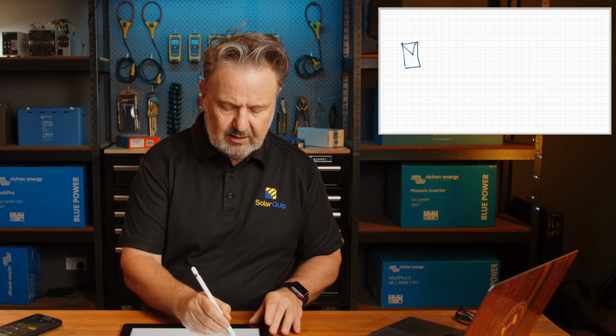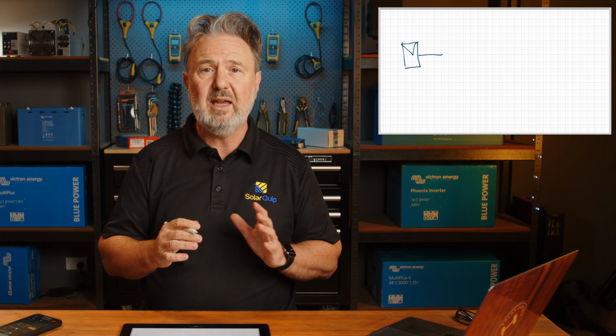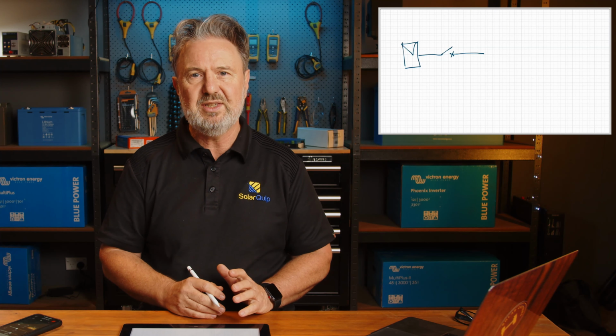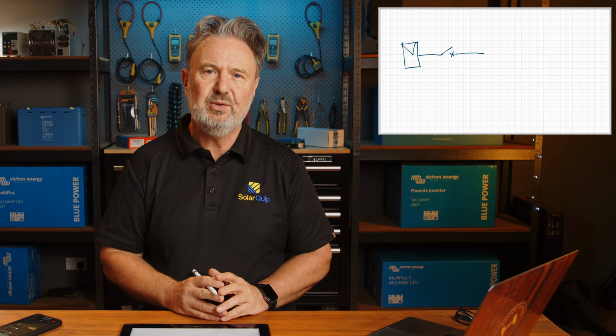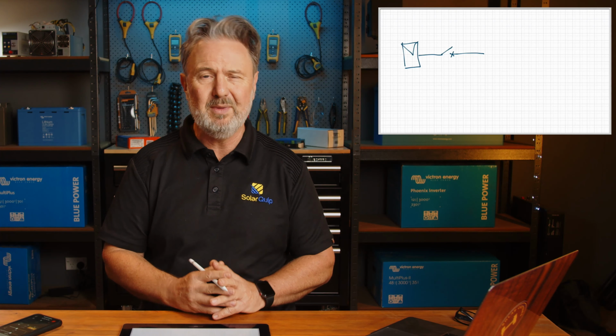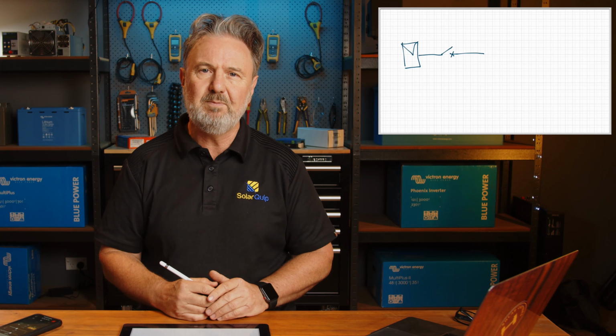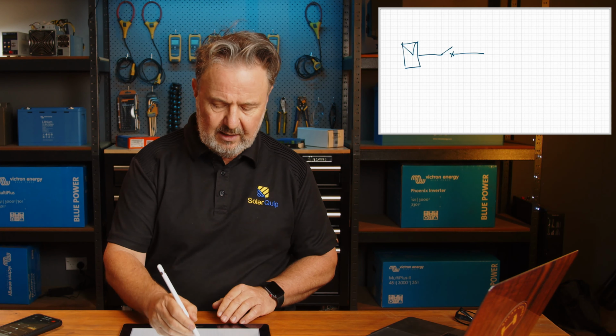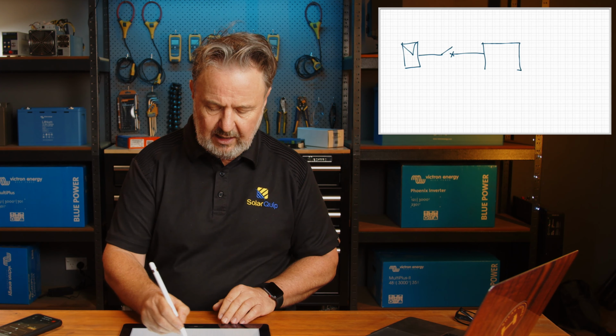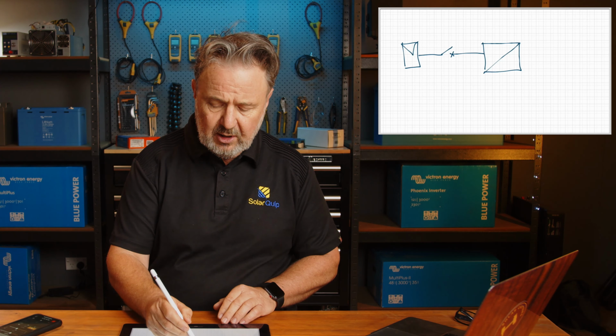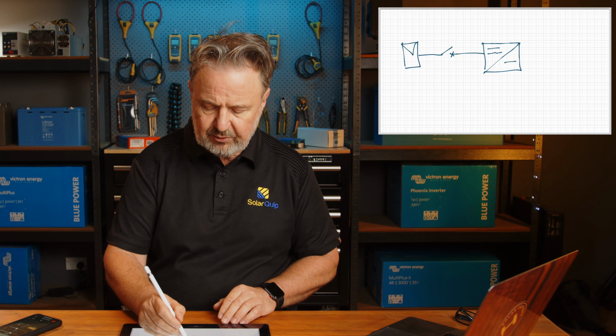We've got a solar array here, connected via an isolating switch or circuit breaker, shown here as an overcurrent protection device. The reason for this is that when you DC couple to a battery system, there's a possibility of backfeed from the battery system. It depends a little on the configuration of the charge controller, but many charge controllers actually have a series connection on one pole straight through to the battery.